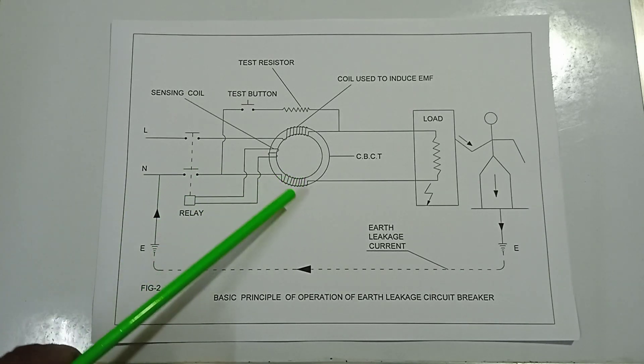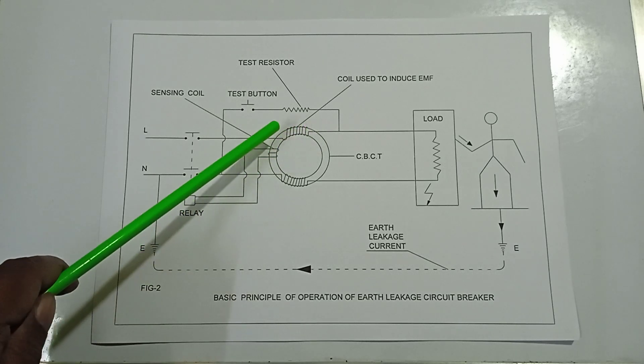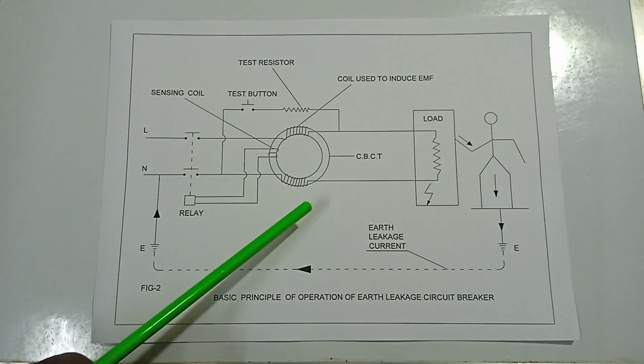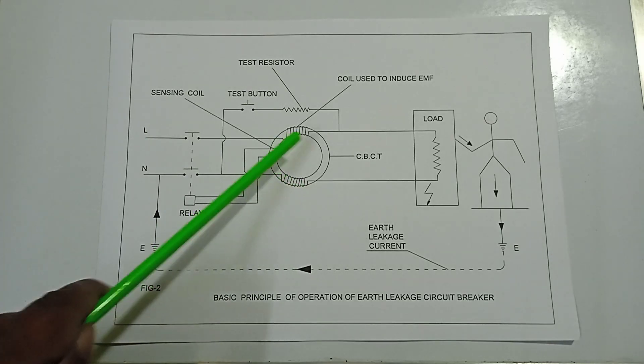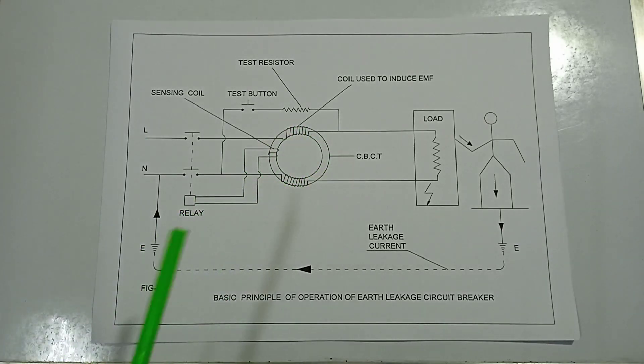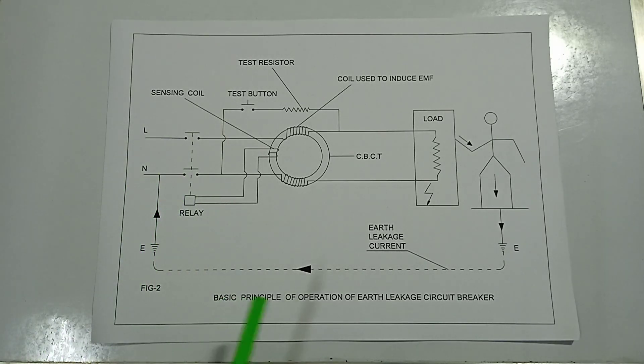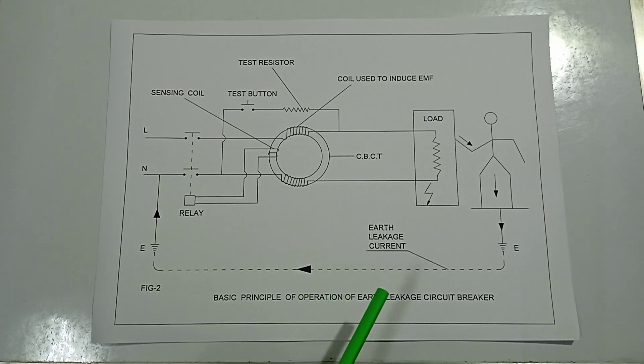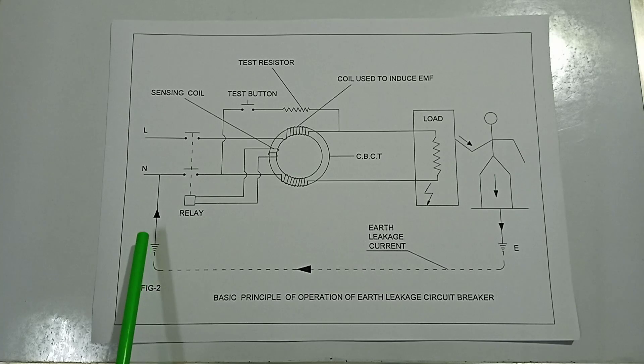The imbalance in the primary circuit of the CBCT energizes the core, inducing alternating flux. This flux energizes the sensing coil, which in turn energizes the relay and trips the breaker. The earth leakage current flows through the human body and returns back through the system earth to the neutral, completing the fault path.